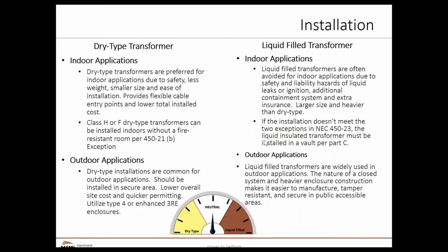And again, with a liquid filled transformer, typically I can only come in on the front of the transformer where I have specifically that wiring compartment. I have fewer options if I'm bringing in buswork or cable. Now, for outdoor applications, a liquid filled transformer by its very nature is an enclosed system. There is, or should be, very little transfer of outside air to the interior of the tank. And for dusty, nasty environments, sometimes a liquid filled transformer has advantages.